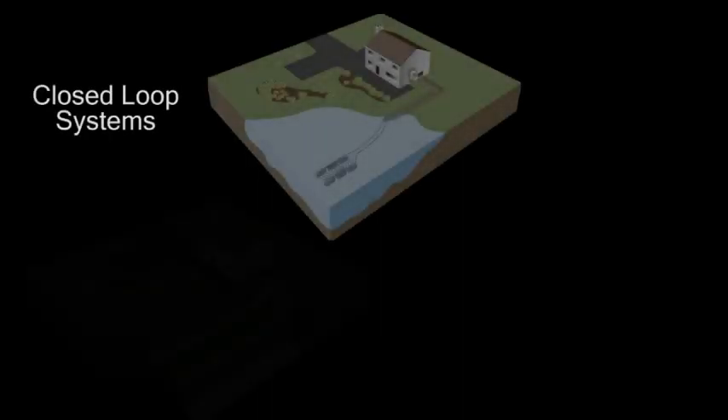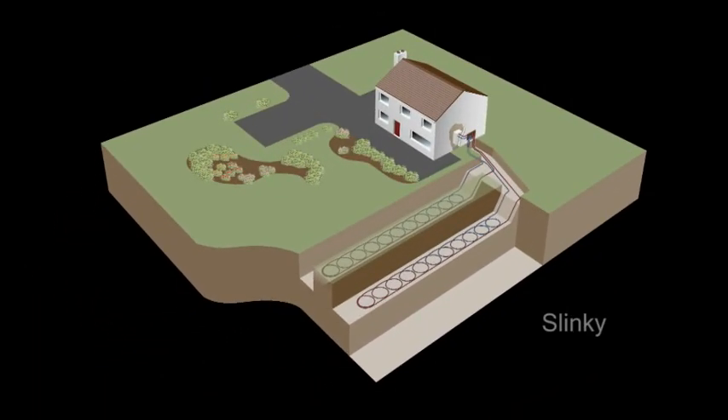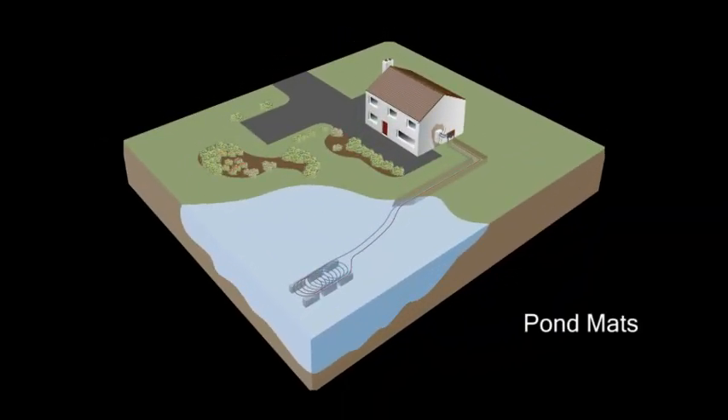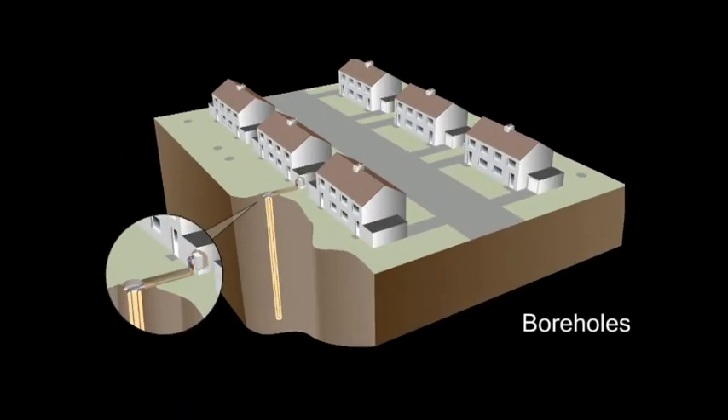When considering ground arrays, you first need to determine the type of array that best suits your property and budget. Kensa typically recommends closed loop systems for most residential and smaller commercial projects. These feature a water-antifreeze mix circulating around pipework buried in the ground or submerged in water. The pipework is either laid in horizontal trenches as straight pipe or coiled slinkies, submerged to the bottom of a water source as slinky pond mats, or inserted as straight pipe into a vertical borehole.